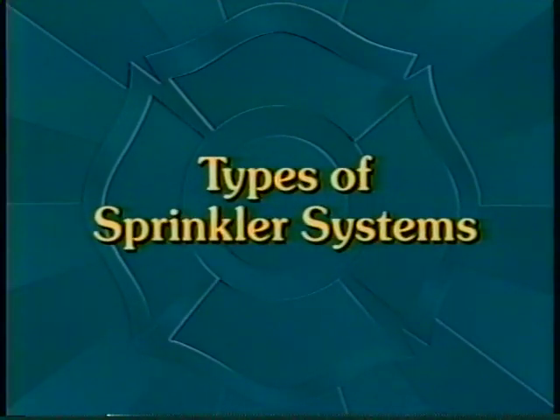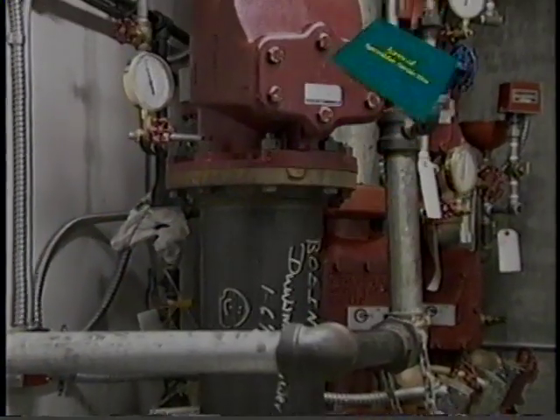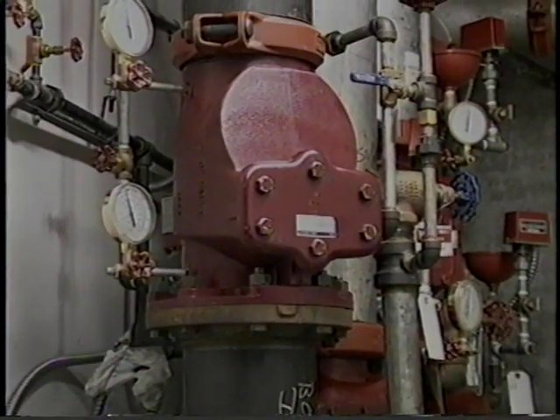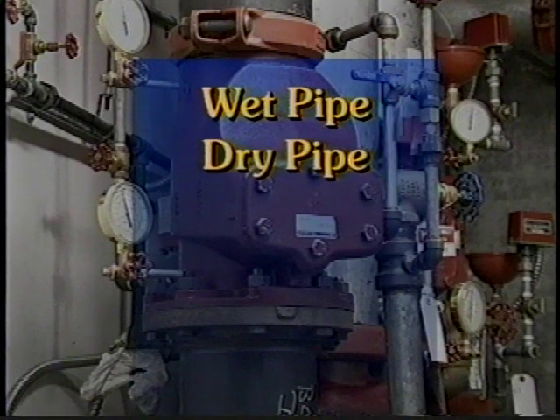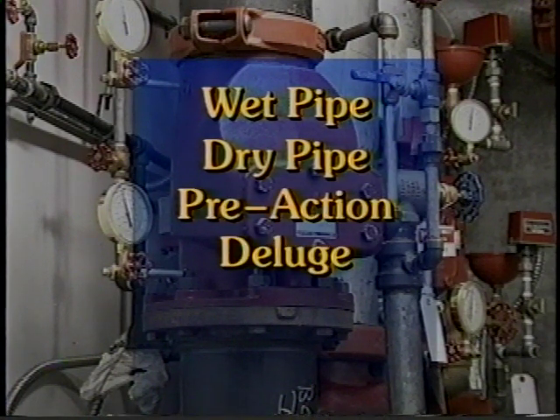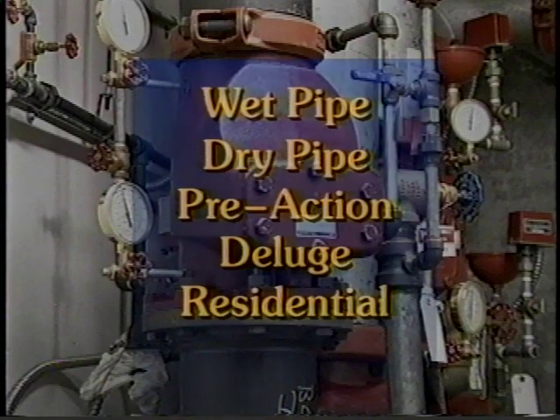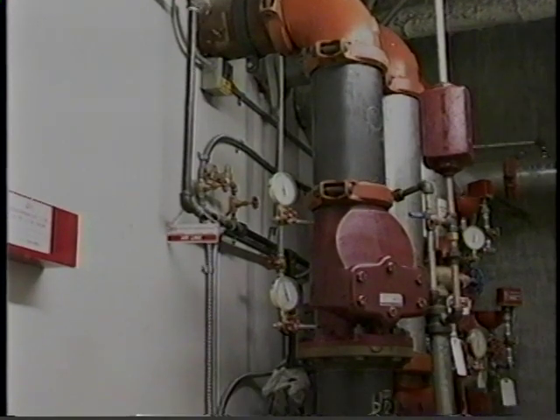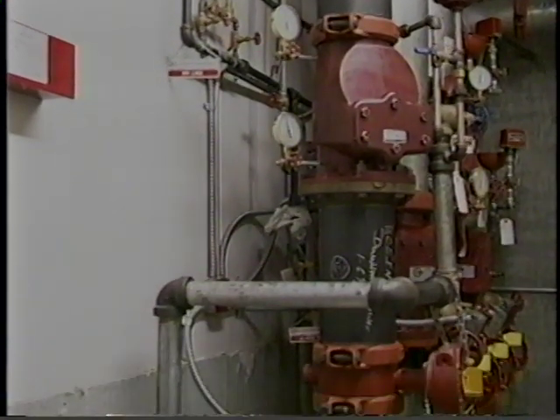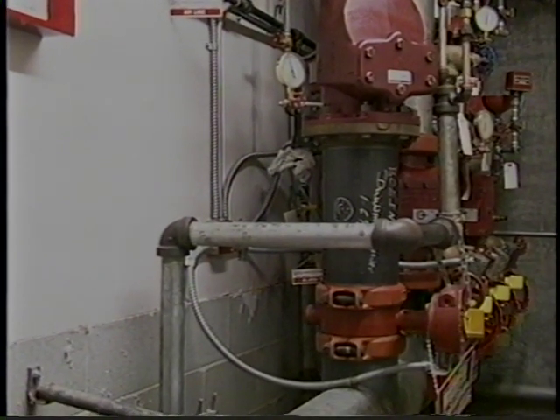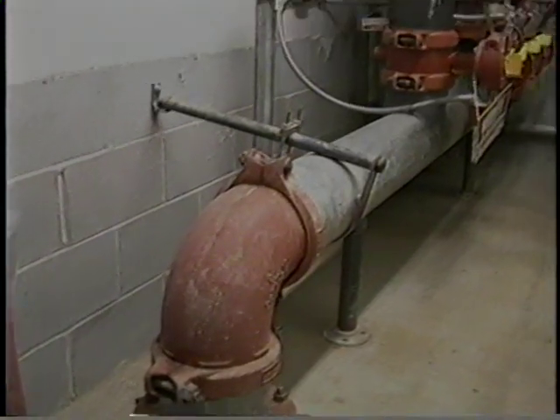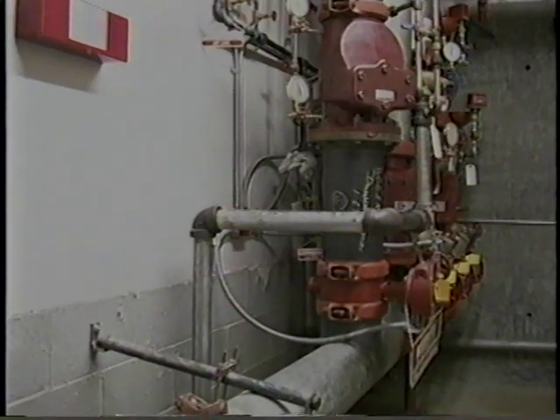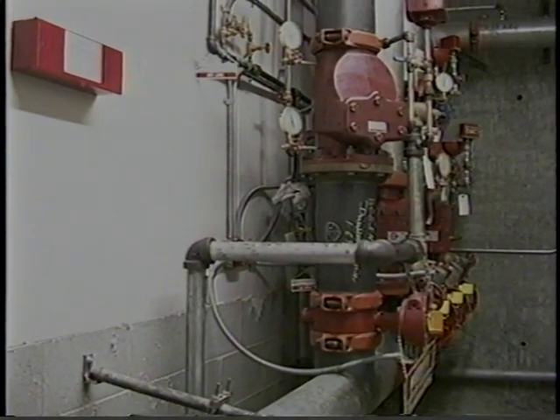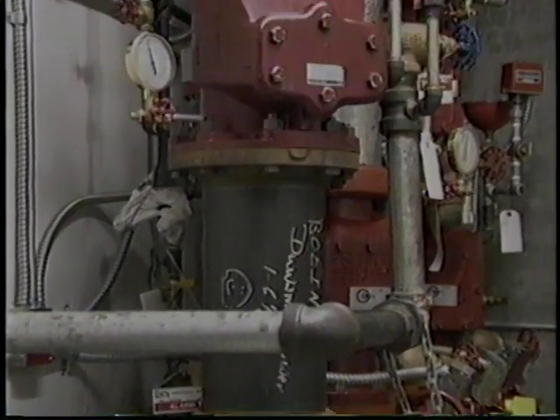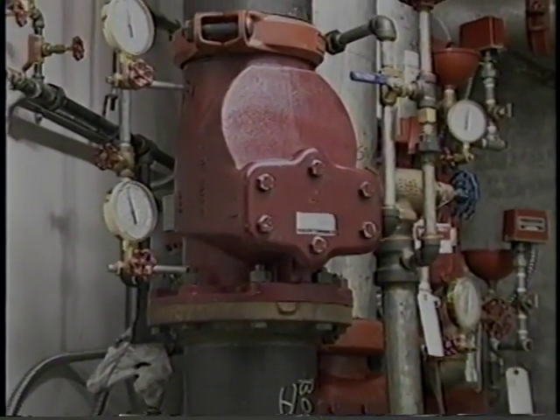Different types of occupancies require different types of automatic sprinkler systems. There are 5 main types of sprinkler systems: wet pipe, dry pipe, pre-action, deluge, and residential systems. A wet pipe system is used in locations where the temperature does not drop below 40 degrees Fahrenheit. It is connected to the water supply and contains water under pressure at all times. This allows an activated sprinkler to immediately discharge water on the fire and set off an alarm.